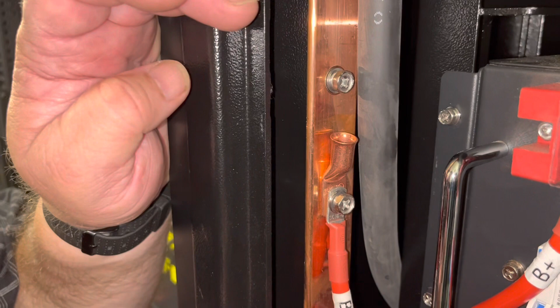Now, I will come back and I will do an IR scan of this entire bank when I get a heavy load on it. But one thing you can't do with an IR camera, at least the ones that I'm familiar with that cost up to $25,000, is get a good temperature reading off this lug, because shiny metal reflects heat from all around it. And when I do the thermal scan, I'll show you what I'm talking about. So to take a temperature reading off this, I would have to paint it, say a black, some type of paint, or put some tape on it real good to where I could get a temperature off that tape. But I'm not going to have to do that because I'm going to get the temperature reading off this right here. And this temperature is probably going to be what the temperature of this lug is.